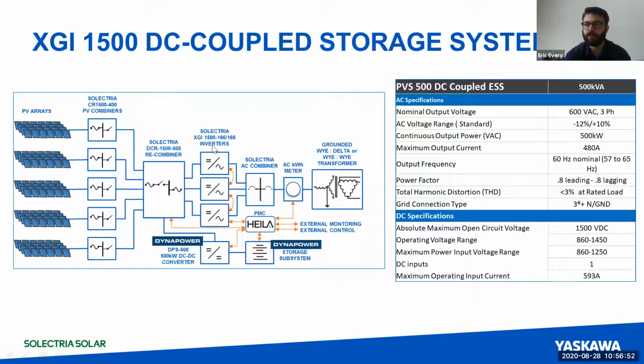Normally for PV, if you put string inverters on the same DC bus, you could damage the inverter. You can blow out the IGBTs, and it's not a good thing. But what we're doing is synchronizing the units. We have a communication cable between the 3 inverters that synchronizes when the IGBTs actually switch. If you didn't do that, the differences in voltage between the inverters can drive current between them. We call that circulating current. If that circulating current gets bad enough, you can damage the IGBTs, which leads to an inverter failure. So by synchronizing the switching to all happen at the same time, we drastically minimize that circulating current and create a stable operating network.